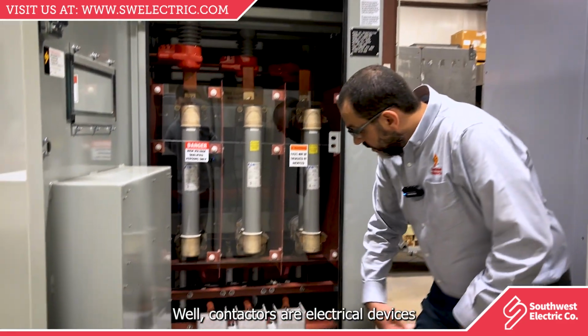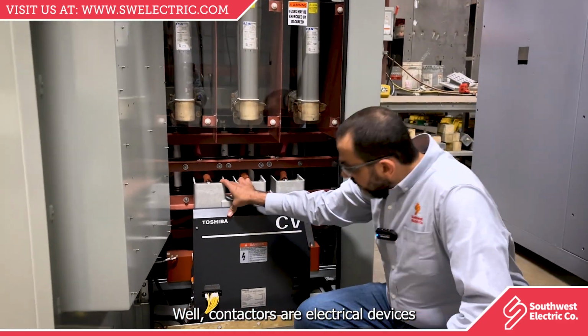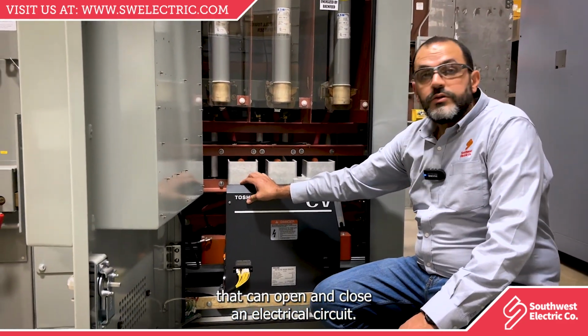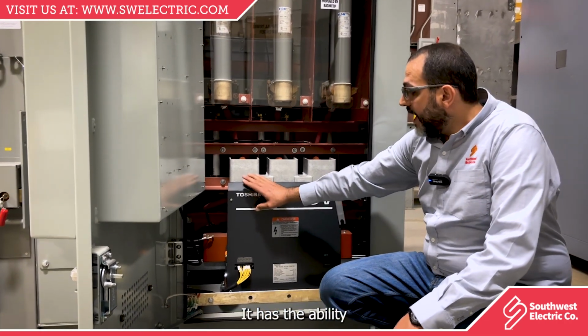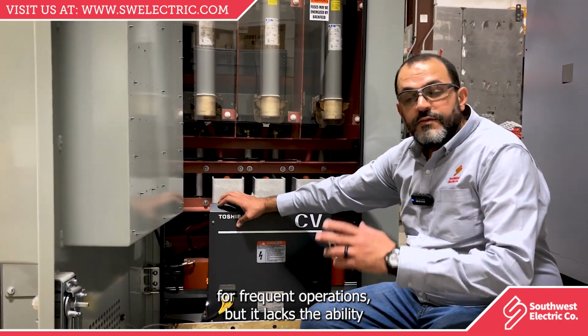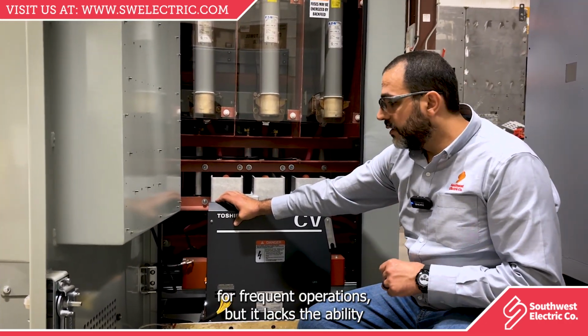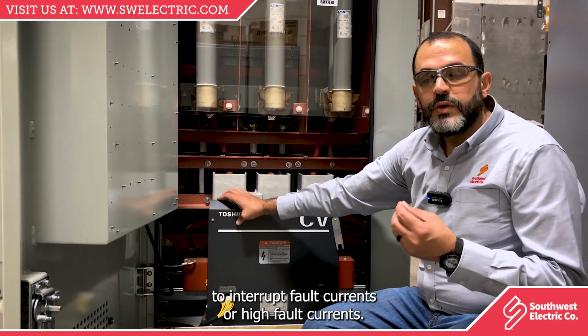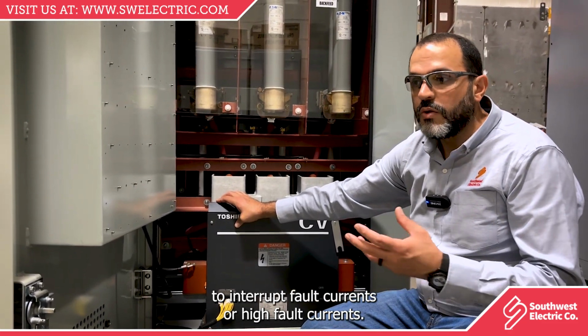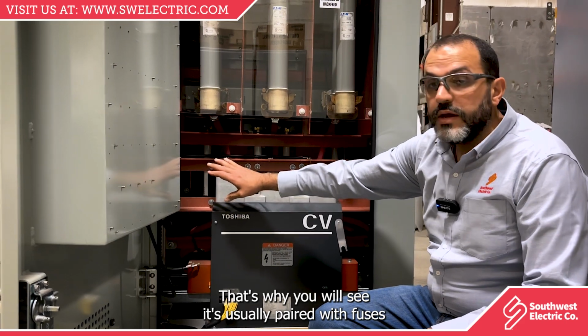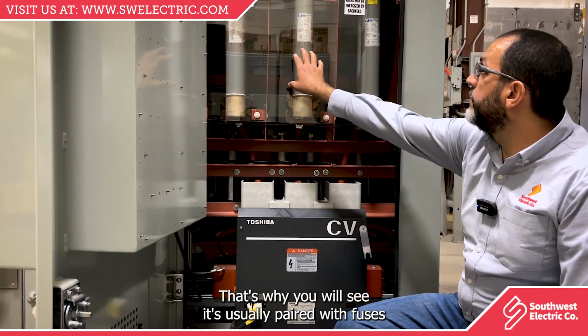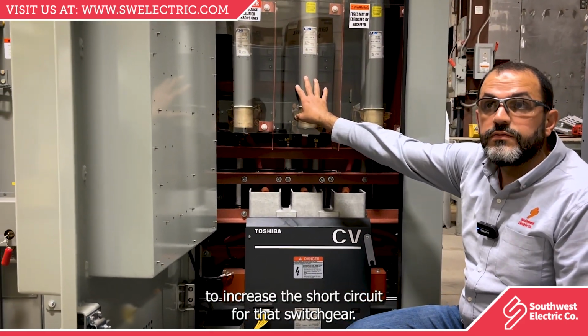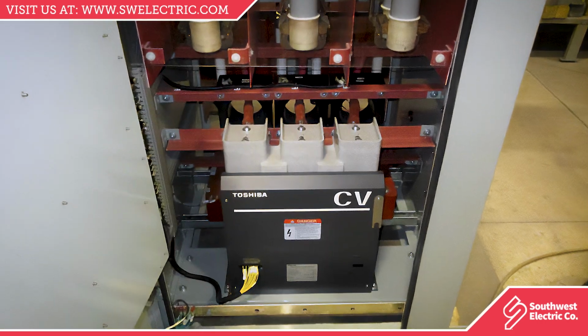Contactors are electrical devices that can open and close an electrical circuit. They have the ability for frequent operations, but lack the ability to interrupt fault currents or high fault currents. That's why they're usually paired with fuses, to increase the short circuit capability for that switchgear.